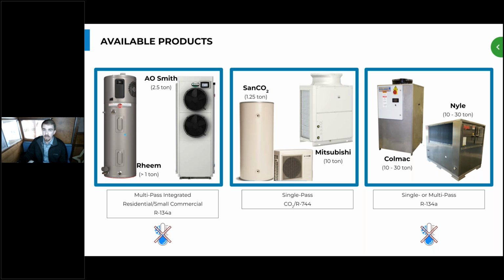So if you're in Hawaii, you might be able to put this out on the roof, or somewhere in the south where it doesn't get below 40 degrees throughout the year. These can be placed outside just fine. But if you're in places like Seattle where you see quite a few days below 40, then you'd need to place it in a buffer space like a garage or provide redundant backup for those days where it drops below their acceptable temperature.